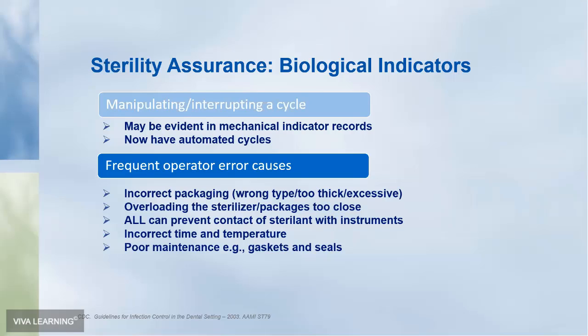Frequent operator error causes are incorrect packaging. You use the wrong packaging. It's too thick, it's too much, it's the wrong type. Overloading the sterilizer. And that's really where the accessories that come with sterilizers are so important.